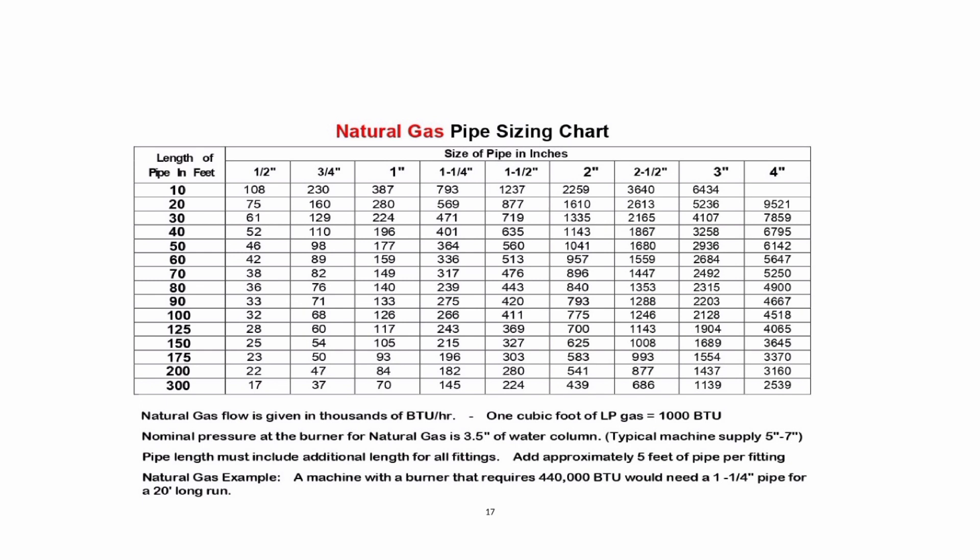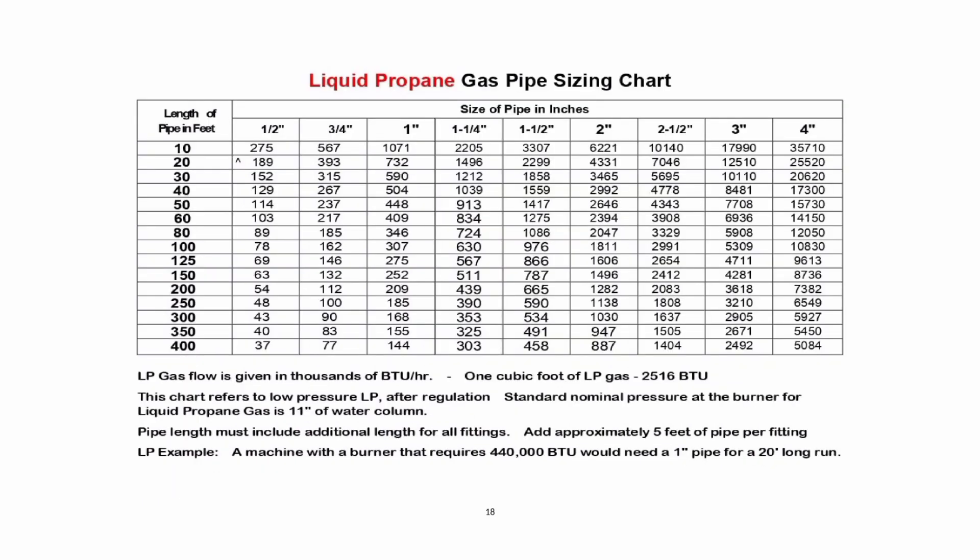Natural gas example: A machine with a burner that requires 440,000 BTU would need a 1-1/4 inch pipe for a 20-foot long run. LP gas flow is given in thousands of BTU per hour. One cubic foot of LP gas equals 2,516 BTU. This chart refers to low-pressure LP gas after regulation. Standard nominal pressure at the burner for liquid propane gas is 11 inches of water column. Pipe length must include additional length for all fittings; add approximately 5 feet of pipe per fitting. LP gas example: A machine with a burner that requires 440,000 BTU would need a 1 inch pipe for a 20-foot long run.